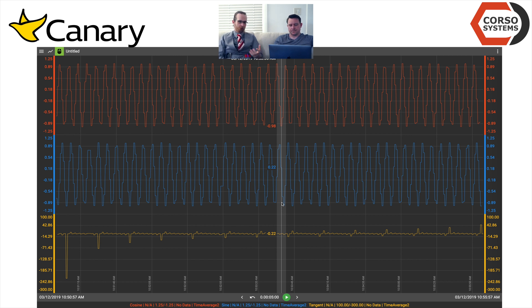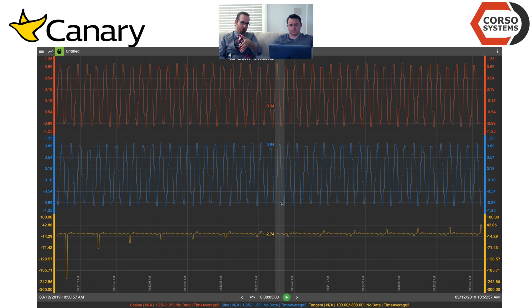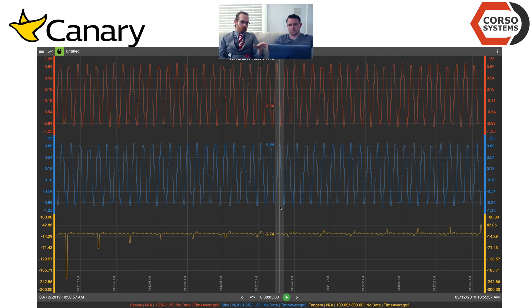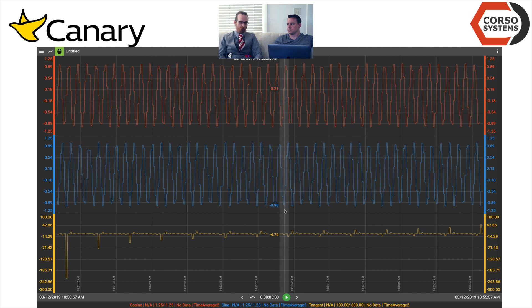It kind of follows the concept of Sparkplug B where you just create your tags in Ignition and everything auto-populates and generates on the Canary side. We're super excited about that. You've seen some of the stuff we've talked about with Bedrock; we've got some Opto 22 Epic Groove coming in, and Siemens is doing some stuff with MQTT. The ability to go from just having implemented a new machine to the Canary historian automatically seeing that and pulling the tags in — and because of the integration with Ignition and MQTT Sparkplug B through a broker, Ignition automatically sees it too — that's hours or more saved depending on the size and tag count.